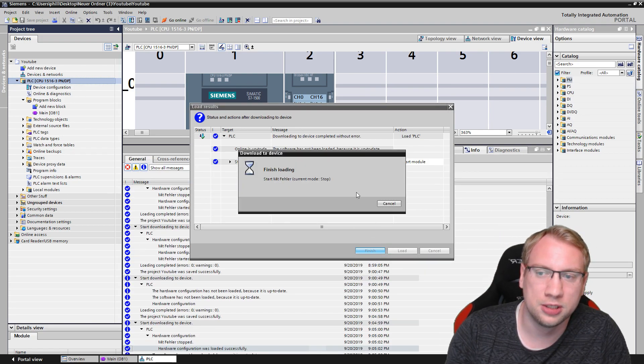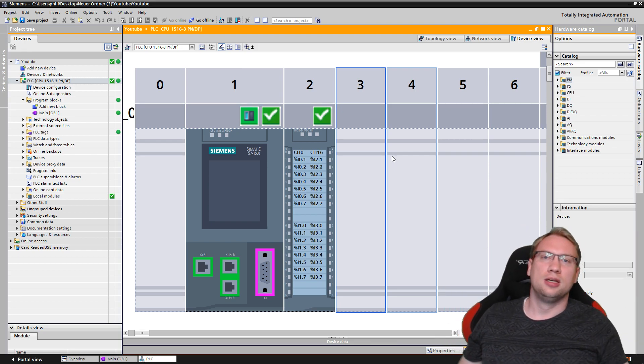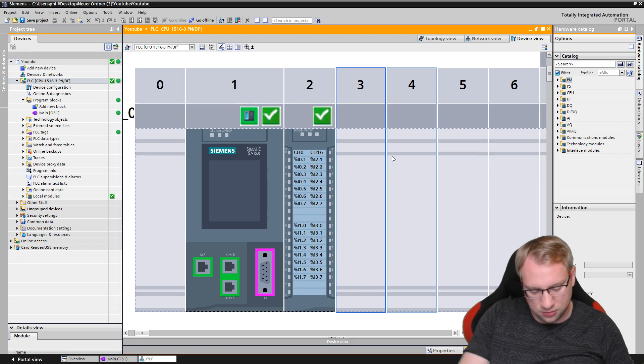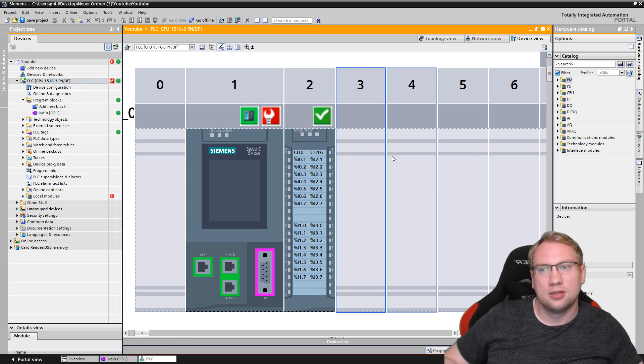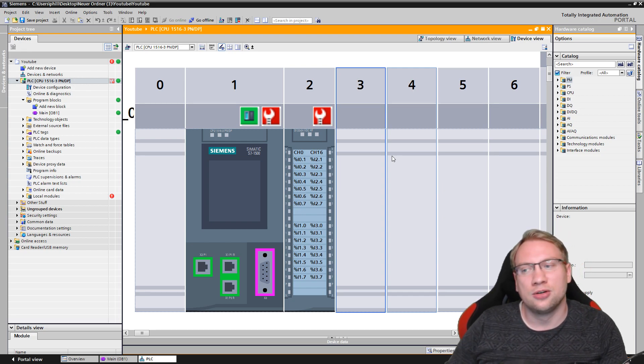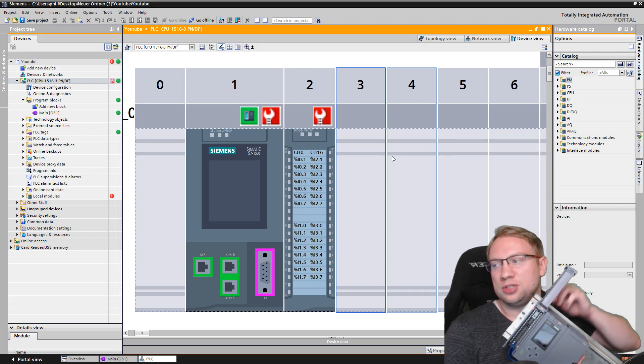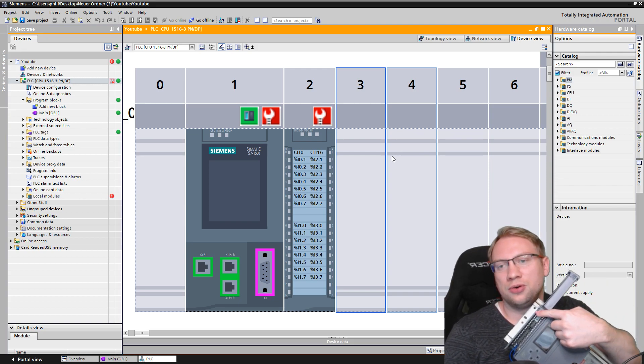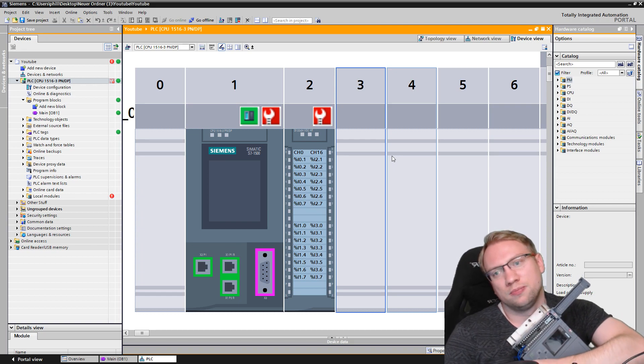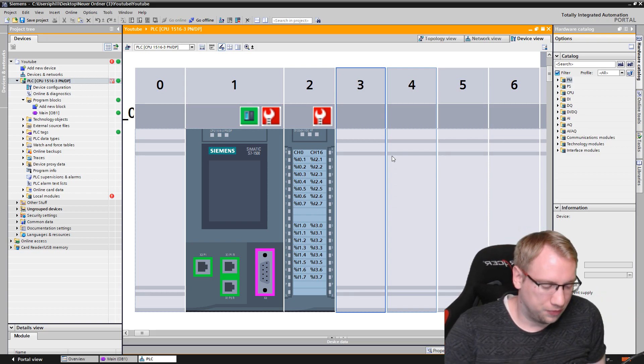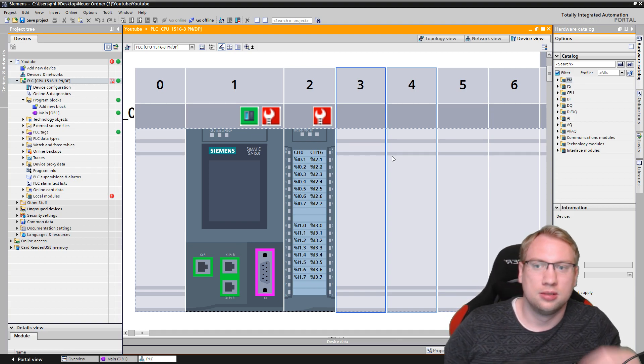I'll download, load, and finish — then go online to see what happens. Everything is green, everything is fine. Now I take my screwdriver and do something — here we go. You can see it turns red. There is a diagnostics problem. I can see this at the physical PLC — red flashing. Channel 16 does not have power because I disconnected the jumper, and channel zero still has power. If I pull the plug, channel zero would also show the error.